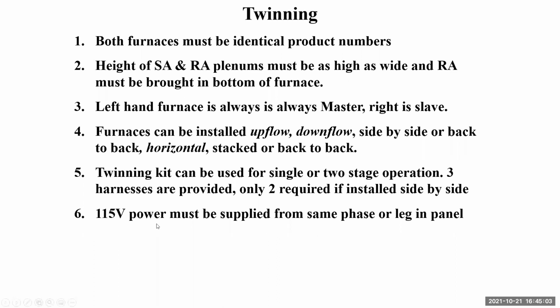And critical number 6, your high volt 115 volts must come from the same phase or leg in the panel. If they're off separate, you're going to get problems.